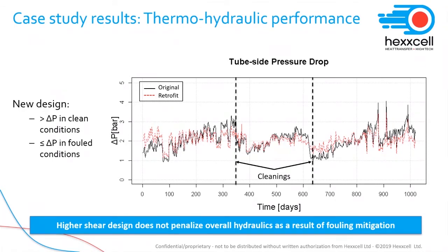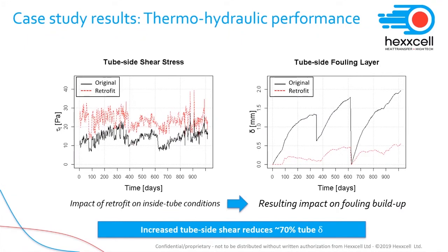Very often, high shear designs that produce higher pressure drops are discarded on the basis that this may affect production. However, this shows that the higher shear design does not necessarily penalize the overall hydraulic performance, and as a result of better fouling mitigation, it could end up being the lower delta P option at the end of run. In fact, while the tube shear stress are indeed much higher than in the original design, as shown on the left-hand side, the higher shear keeps the fouling thickness, shown on the graph on the right, 70% lower than in the original design, thus reducing the overall hydraulic impact.